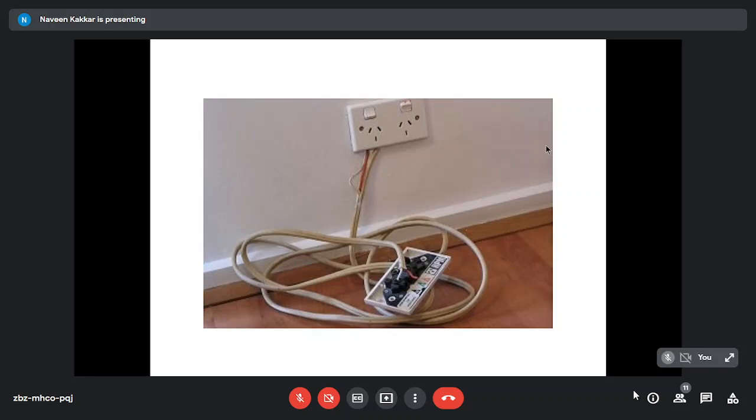We had one episode in our hospital earlier in CMC where platelet counts were high, and all the engineer did was fix the connection and take out the loose ends, and the spuriously high platelet count went away. So the noise, the buzz that the electronic interference creates, is in the smaller volumes, the platelet volumes. So that can be one area of concern.